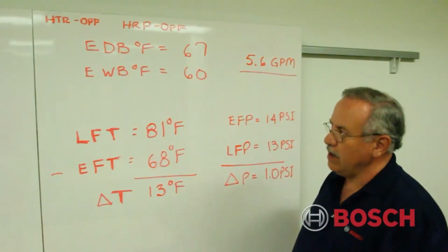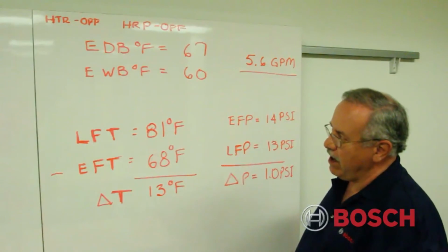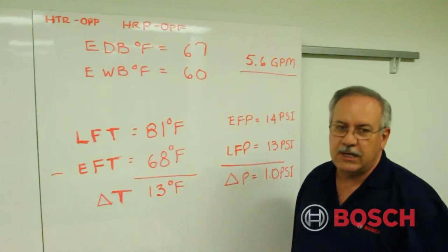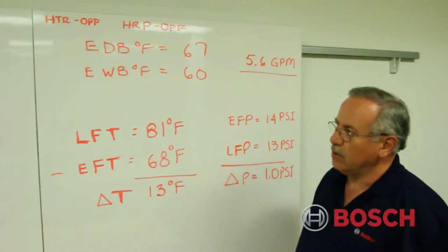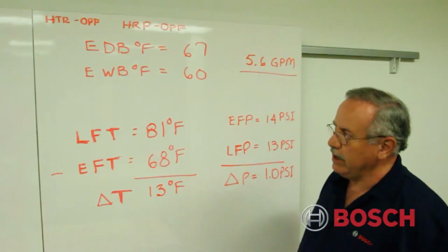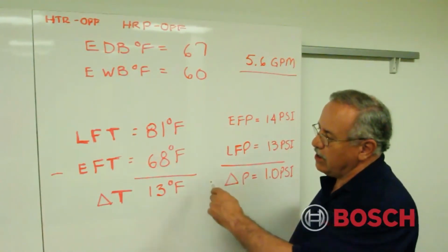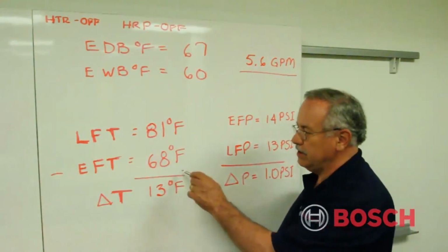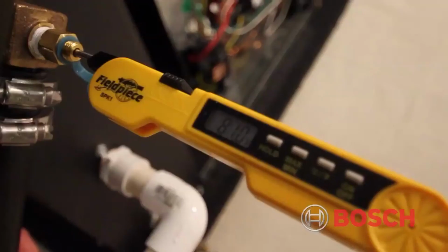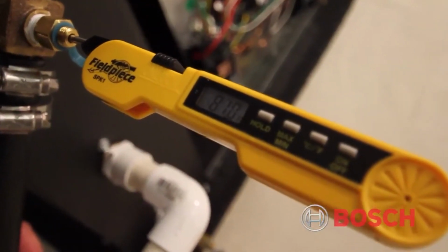All of these must be in the off position. What Mark has found by taking the PT ports, or pressure temperature ports, on the coaxial entering and leaving, he has determined that the entering fluid temperature is 68 degrees. He's also determined that the leaving fluid temperature is 81.